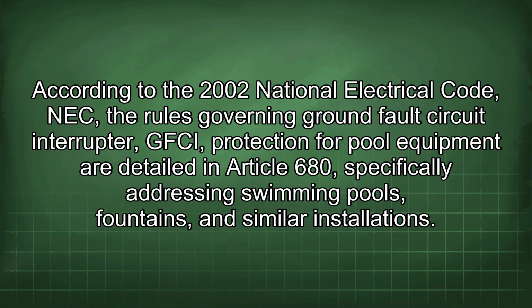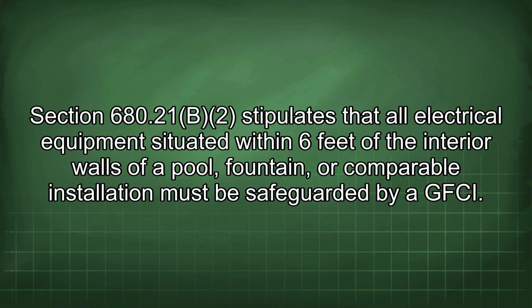According to the 2002 National Electrical Code, NEC, the rules governing ground fault circuit interrupter (GFCI) protection for pool equipment are detailed in Article 680, specifically addressing swimming pools, fountains, and similar installations. Section 680.21(B)(2) stipulates that all electrical equipment situated within 6 feet of the interior walls of a pool, fountain, or comparable installation must be safeguarded by a GFCI.